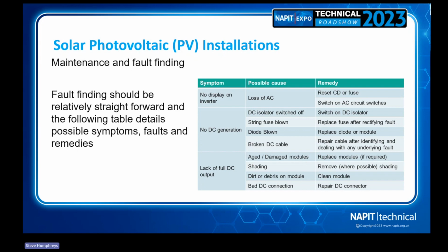If you're fault finding, that approach for an electrician is pretty straightforward. You've got to have a symptomatic approach. You look at the symptom - normally the client would tell you, 'I'm getting no generation, the inverter display's gone off,' whatever it may be. You'd investigate the possible cause of why that might be, starting with the most simple things. Could be that someone's just switched off the DC isolator, or an MC4 connection's come loose and disconnected, and then obviously you'd find the remedy to put that right.